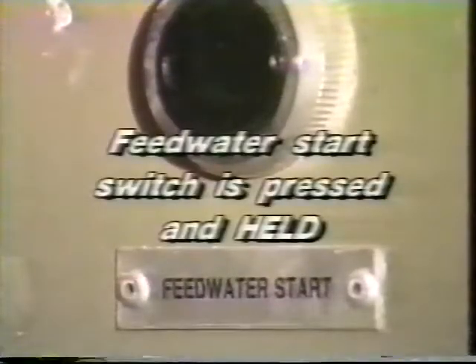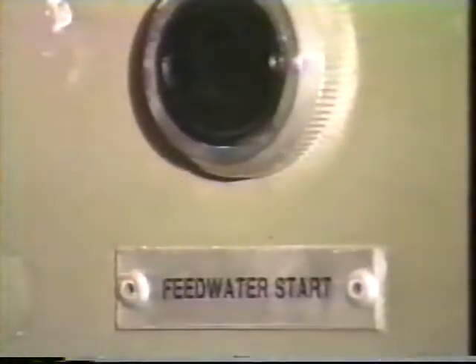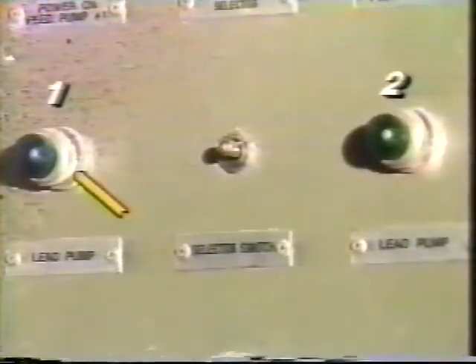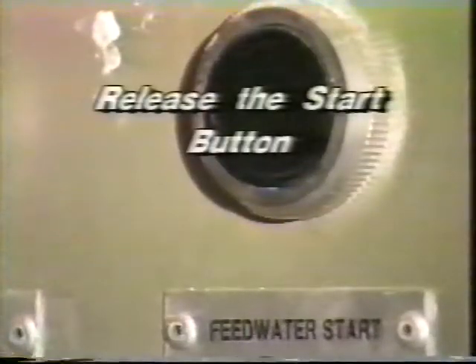Next, the feed water selector switch is placed in the number 1 position. The feed water start switch is pressed and held. This energizes the feed water start relay. When the feed water pump light comes on and the feed pump is delivering water through the number 1 feed water pump flow switch, the start button is then released. The same sequence occurs if the feed water selector switch is set in the number 2 position. The transfer of these lights indicates that an automatic changeover has occurred.